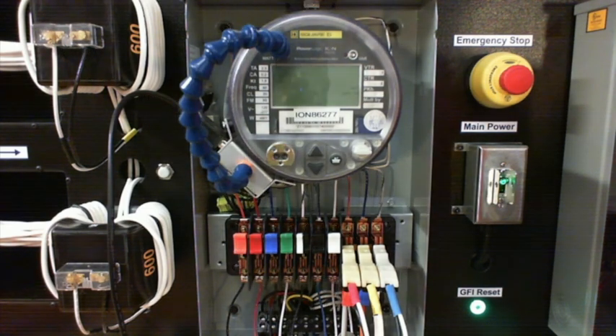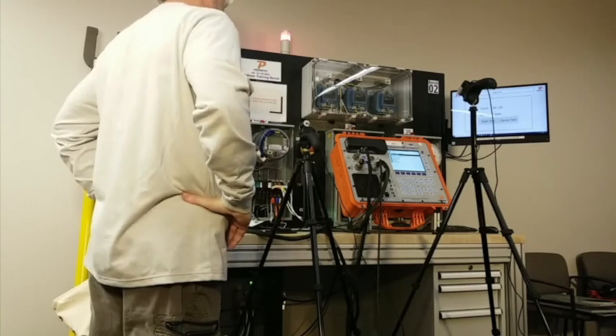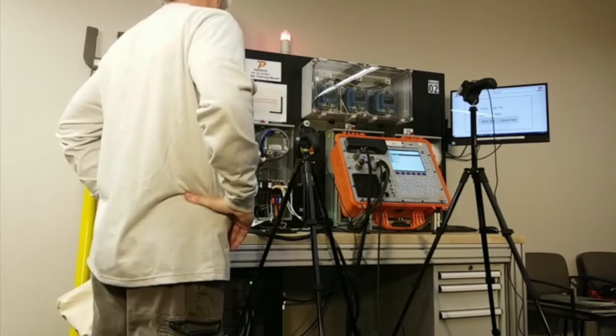Okay. Now we're doing substation testing here for testing meter. So what happens there? We know that we want to isolate. We have to open up everything because if I were to leave everything connected at that test switch and I accidentally got some that went back into the system, okay, and I could trip a relay, we'd have a serious problem. Okay. You start seeing hard hats you don't normally see showing up at the substation, want to know what's going on. Okay? So we definitely don't want that to happen.